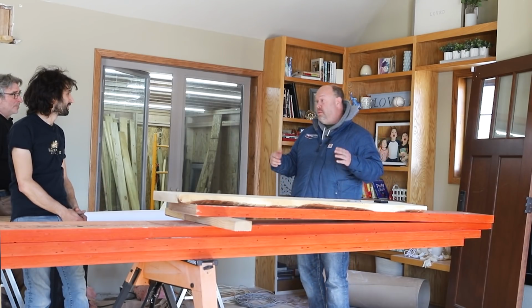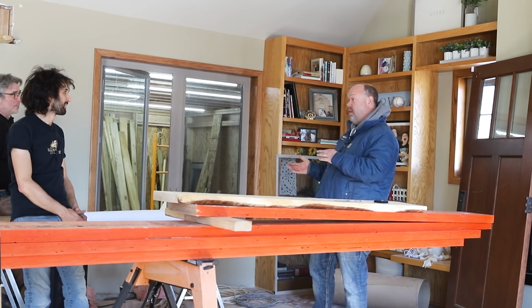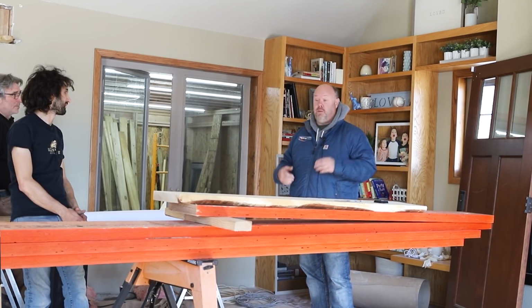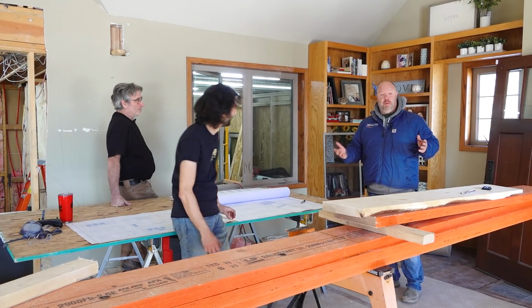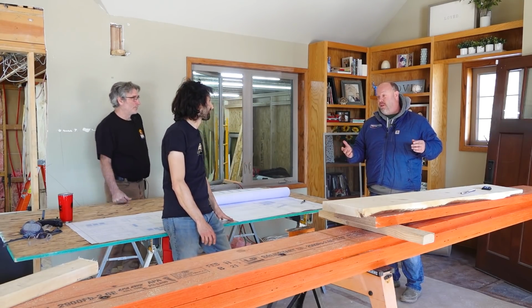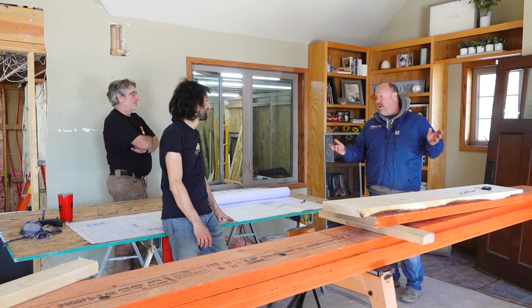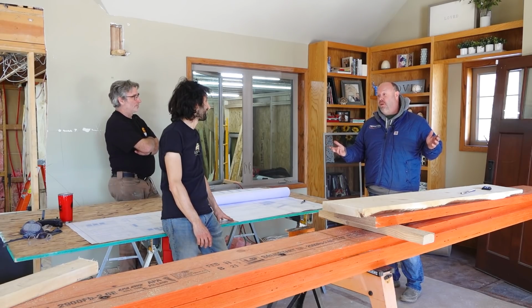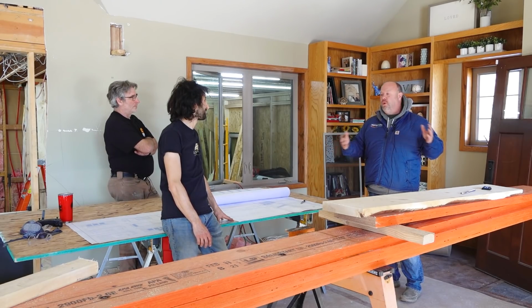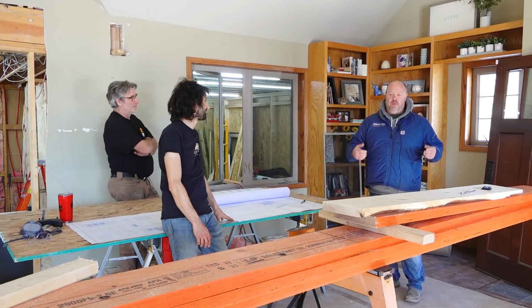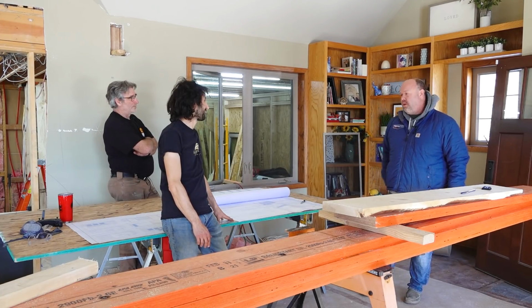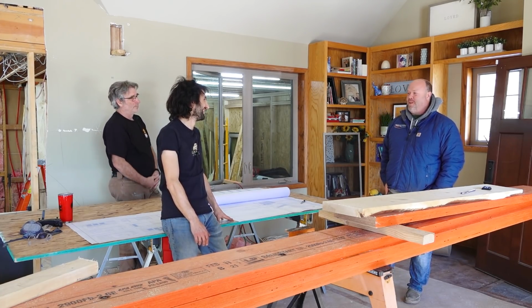So like this room here, it's about 600 square feet, that's going to need a different amount of heating and cooling than somewhere else that's maybe 200. Correct. Or you could have two rooms that are both 600 square feet - one could be interior, or one could have one outside wall versus one with four outside walls. One could be facing south and west with 80% glazing glass on that wall, so your solar gain would be massive. There's no rule of thumb out there - I can't say for every square footage this many BTUs is needed. There's just way too many variables.